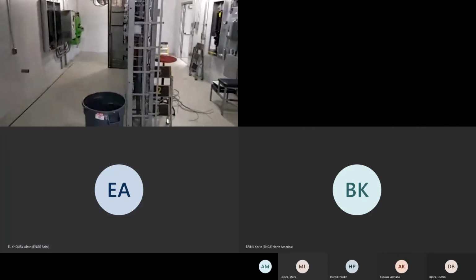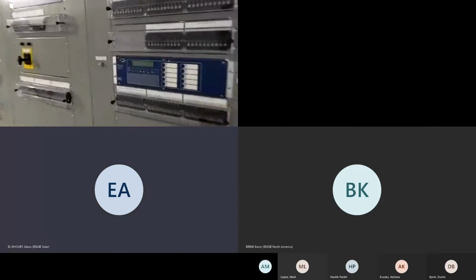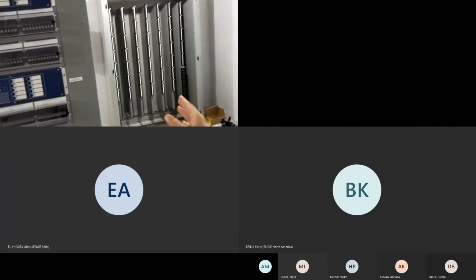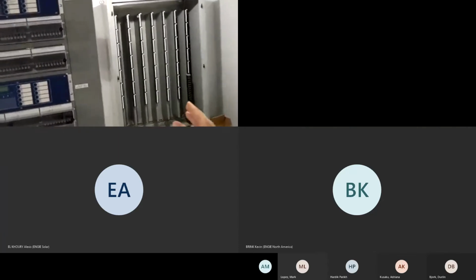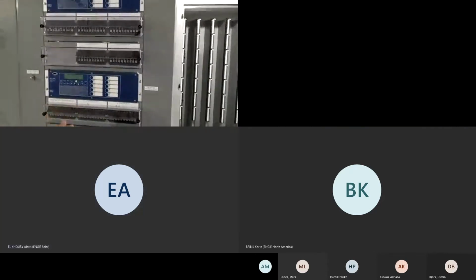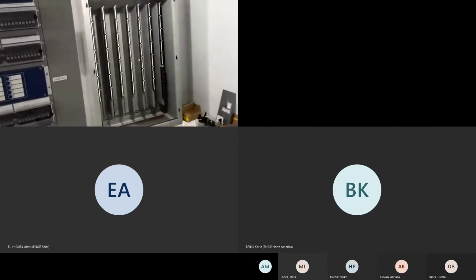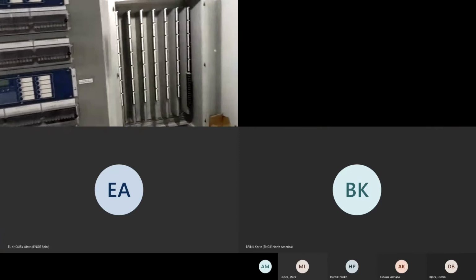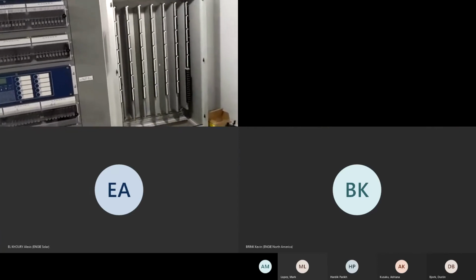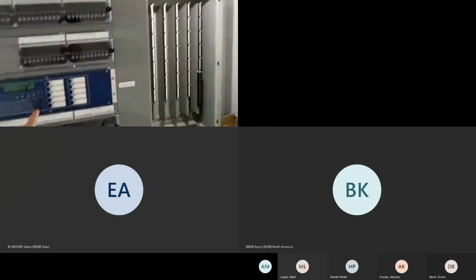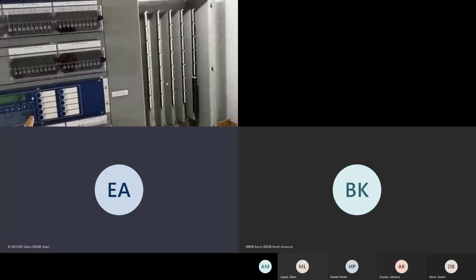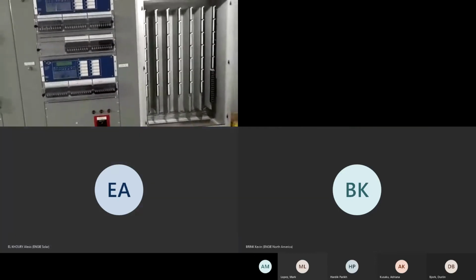They'll do functional testing, but no longer on the relays themselves. What they'll do is at the terminal cabinet, they'll say, okay, we see a phase imbalance over here, and they typically rotate the phases using an Omicron input, then come over to the relay and check: do I see the phase imbalance here at the relay? The answer is yes, so that should operate or send a signal, continuous or discontinuous, to a different terminal block and force something to operate out in the field. We can't see whether the thing in the field actually works, but we can monitor whether that signal is sent. It senses the condition, the relay sees the condition, and sends the response. That's the type of testing we do here. We don't test the physical relay anymore because we know that was already done by our guys in relay testing. Does that make sense?